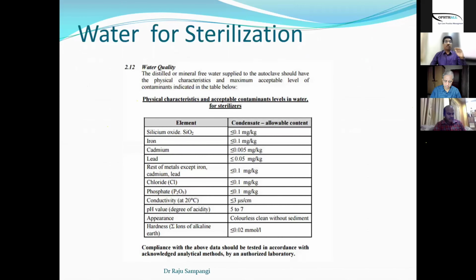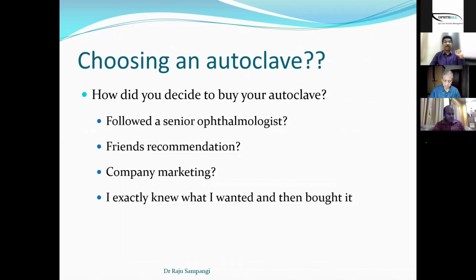Coming to the water quality, this is what has been suggested. You have to use distilled or mineral-free water during the autoclave, and these are the various parameters that are there. And the pH value is slightly set at 5 to 7. Acidic is recommended in this document.